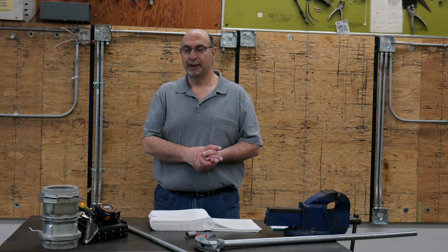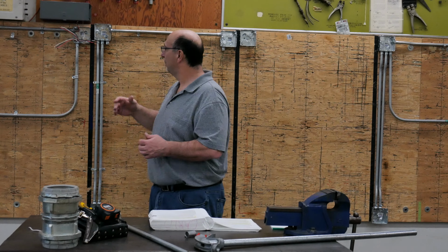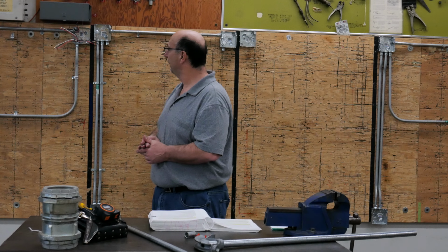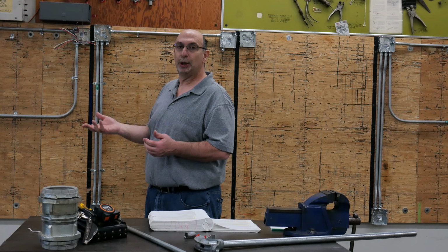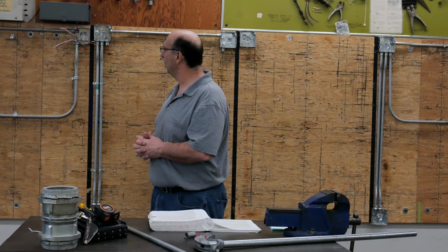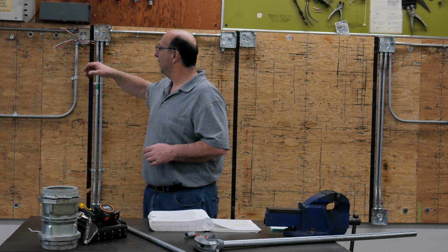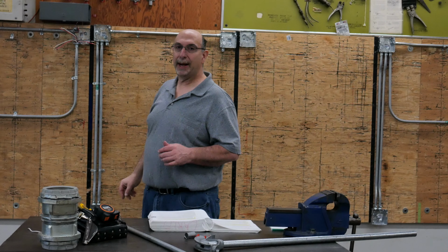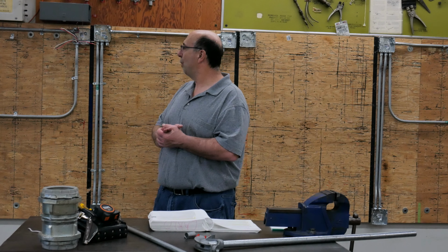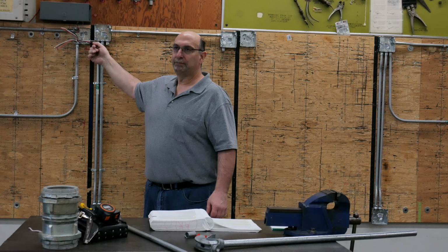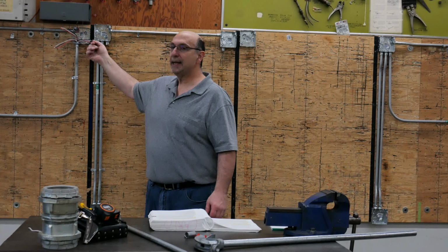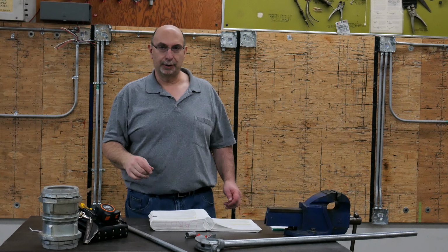How many of you have used pulling lubricant to pull, for example, wires through or conductors through a raceway? Gets pretty tough, right? So they do actually make these things called pulling lubricants. You purchase them from the wholesaler, you wipe them on the wire, and it makes pulling the wire through the raceway way easier. But whatever you get, make sure it does not have any damaging properties that will damage the insulation on the conductors.